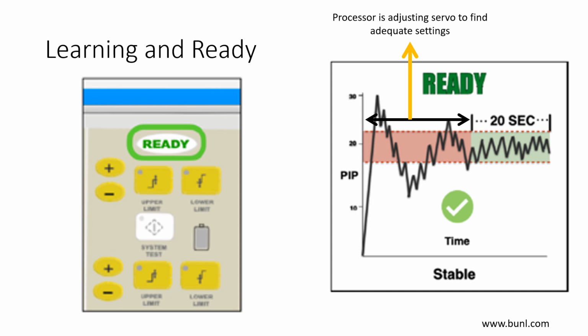This usually happens within 45 to 90 seconds, but can take up to 3 minutes. After the ready condition is achieved, the alarms are calculated at 20% above and below the servo pressure. Alarms can then be manually adjusted. Pressing Enter will recalculate all of the manually adjusted alarms.